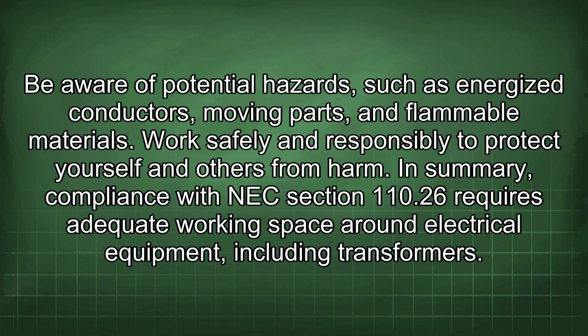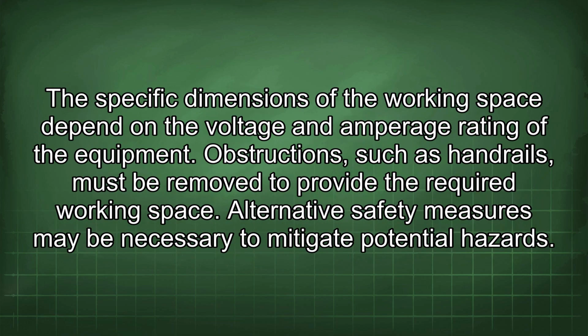In summary, compliance with NEC Section 110.26 requires adequate working space around electrical equipment, including transformers. The specific dimensions of the working space depend on the voltage and amperage rating of the equipment. Obstructions, such as handrails, must be removed to provide the required working space. Alternative safety measures may be necessary to mitigate potential hazards.